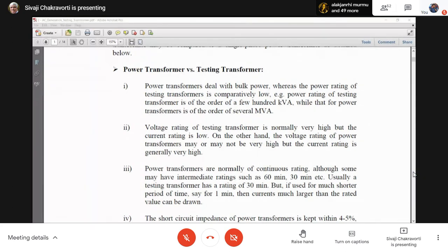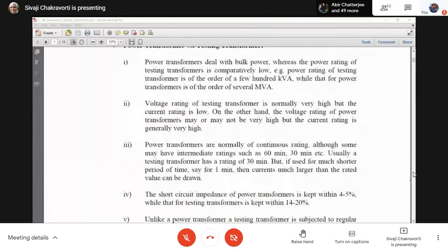So the big difference between the power transformer and the testing transformer is that the power transformer's voltage rating is high, but its power rating is also very high. Testing transformer voltage ratings are in fact even higher than the power transformers, but their current rating is very low. So their power rating will be comparatively lower. This is the first difference. Okay, the first and second I have talked about together.